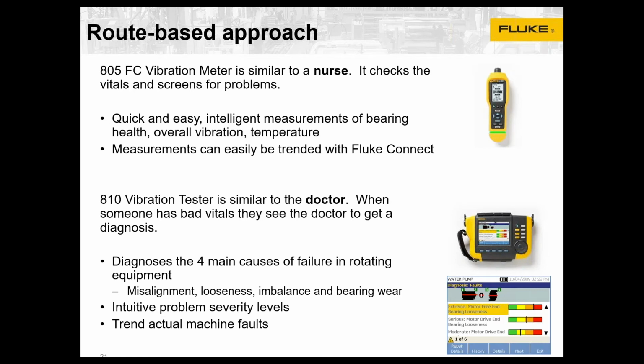So you might see bearing wear, but it will also call out faults, for example, for misalignment, if that's the root cause. And you can trend faults over time. So maybe you see that you have a moderate type of fault. It might make sense over time to look and see how quickly that moderate bearing fault is getting worse, for example.